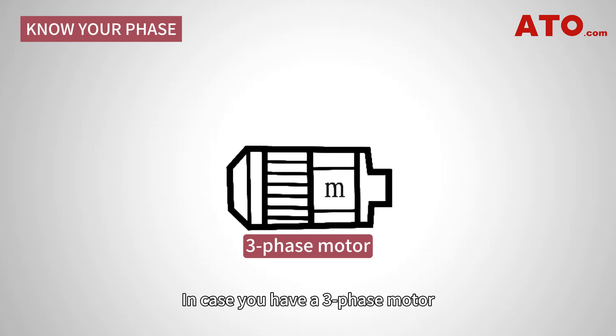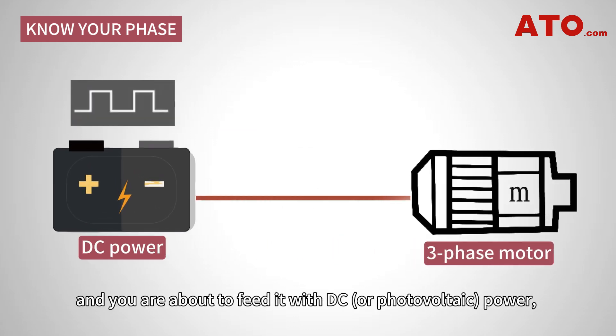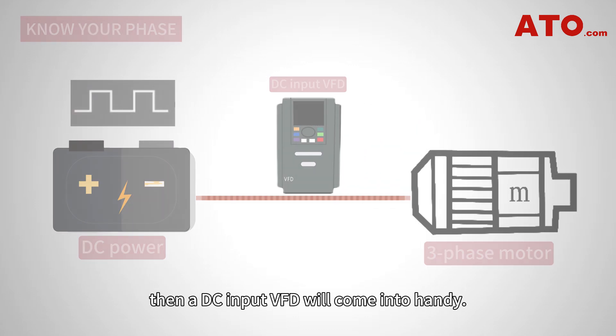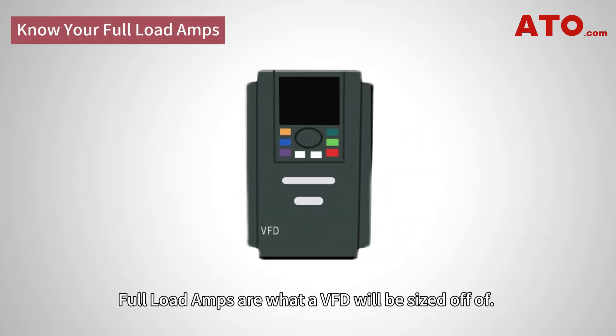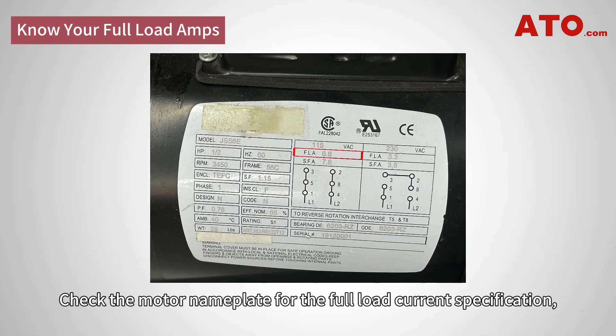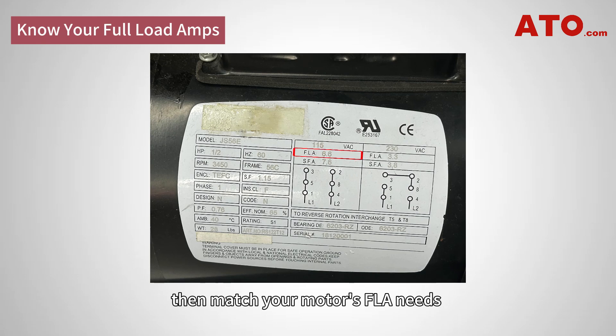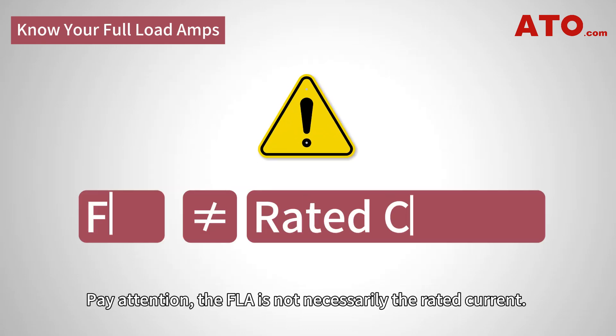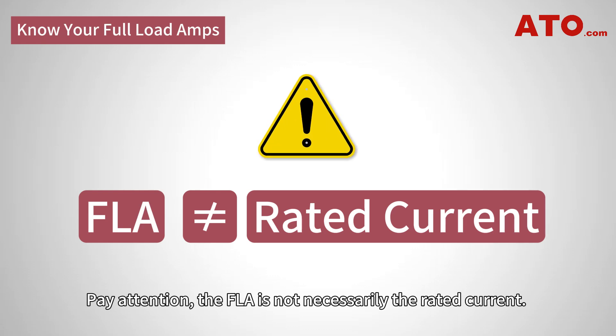In case you have a three-phase motor and you're about to feed it with DC or photovoltaic power, then the DC input VFD will come in handy. Full-load amps are what a VFD will be sized by. Check the motor nameplate for the full-load current specification, and match the motor's FLA with the minimum amp ratings of your target drive.